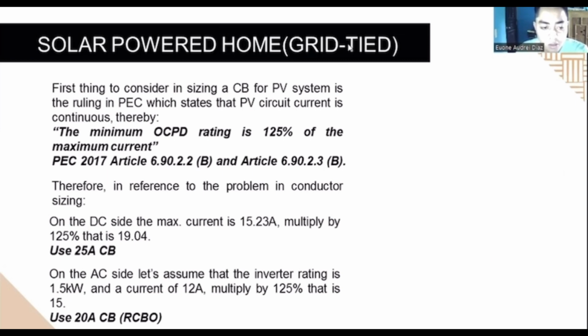On the DC side, the max current is the 15.23 ampacity multiplied by 125%. That is 19.04. Use 25 ampacity CB. On the AC side, let's assume that the inverter rating is 1.5 kW and a current of 12 ampacity multiplied by 125%, that is 15. Use 20 ampacity CB or RCBO. Ang RCBO daw po is residual current breaker with overcurrent.